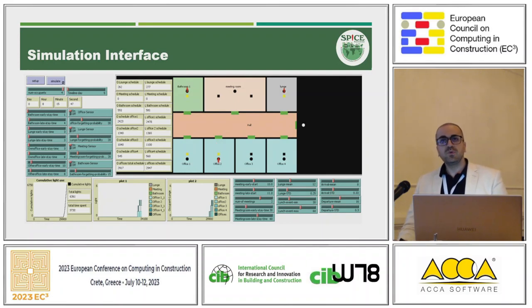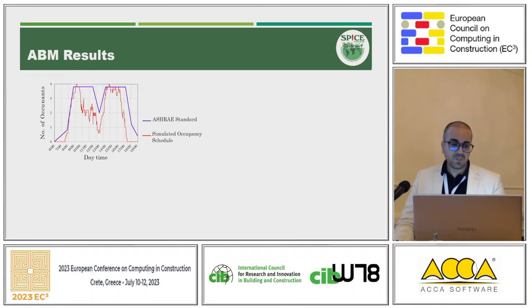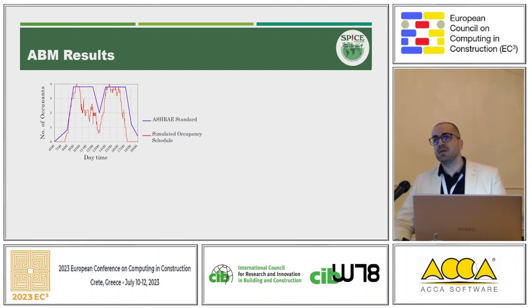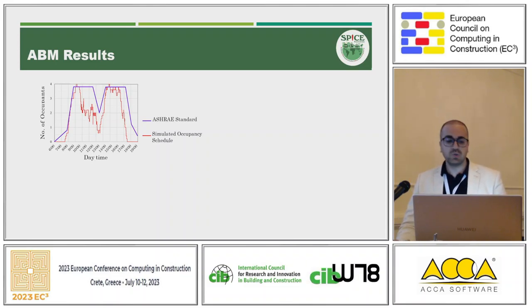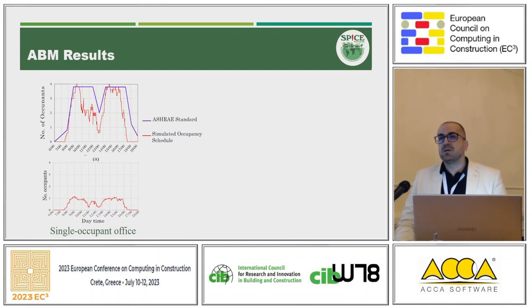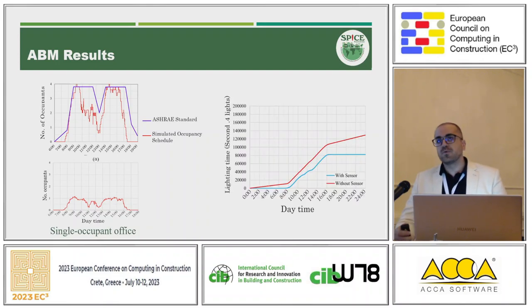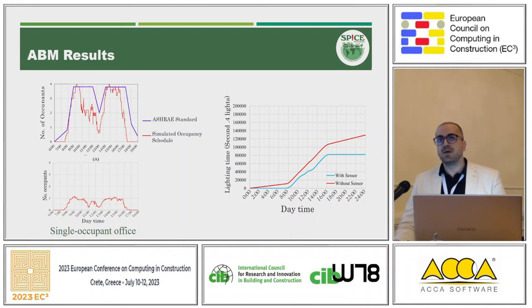The green boxes are the inputs we defined for this simulation and the yellow boxes are the outputs. The results of agent-based modeling show our dynamic schedule in red lines compared to the ASHRAE standards that most energy simulation tools in the U.S. use. For each office, we derived an average occupancy from our inputs and then the amount of lighting energy consumption based on the type of lights assumed. In both scenarios — with or without occupancy sensors — results show that with occupancy sensors, lighting energy consumption can be reduced by up to 50%.